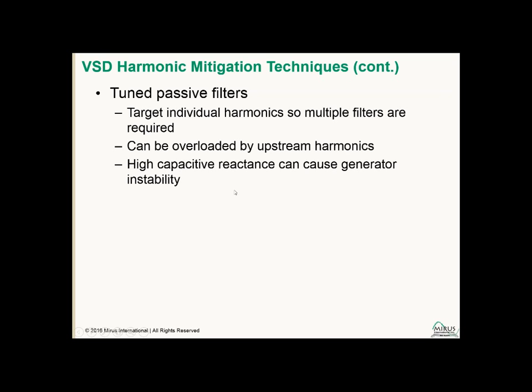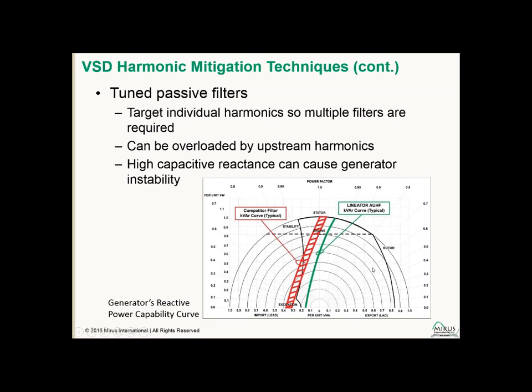problems with generators. This graph here just shows a typical generator's capacitive or reactive capability curve, and on the left side is the capacitive reactance, and if you're outside of this envelope, the internal envelope, this is where the generator will operate properly. If you're outside of that envelope, you're going to have excitation control problems and problems with the generators. And virtually any tuned passive filter, at light loads, is going to be out on this level, and the generator is going to have problems with that. So we definitely would not recommend a tuned passive filter.